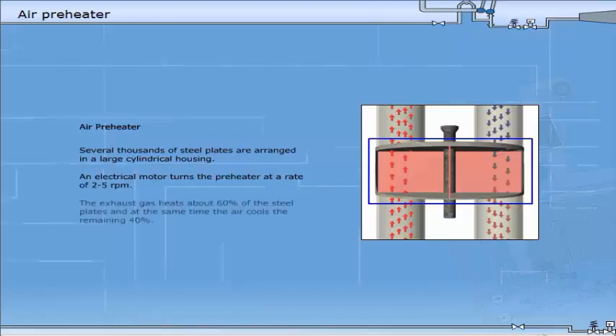To minimise the loss of energy in the exhaust gas, several types of air preheaters have been developed. Ljungstrom's rotating air preheater is one common type. Several thousands of steel plates are arranged in a large cylindrical housing. An electrical motor turns the preheater at a rate of 2 to 5 revolutions per minute. The exhaust gas heats about 60% of the steel plates and at the same time the air cools the remaining 40%.